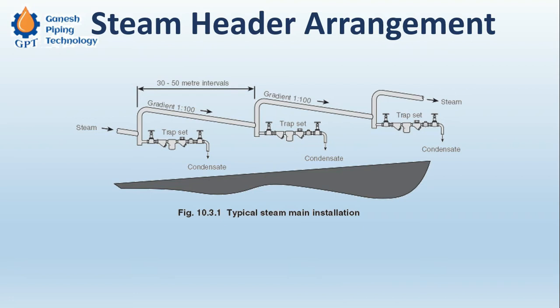At every 30 to 50 meters of distance along the pipe rack, a steam trap is installed. The reason is that steam loses heat as it travels — even though steam lines are insulated, there is always some heat loss to the atmosphere. Because of this heat loss, condensate — liquid water — is formed, and this water travels along with the steam.